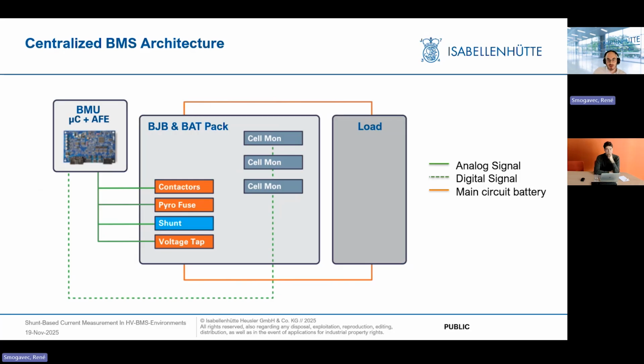So going into the architectures, between the extremes we have the centralized and the decentralized. In the decentralized architecture, the components communicate high quality signals in digital format to each other, such as over CAN bus. In centralized, the sensor and actuator data signals are processed centrally, handled and controlled by the BMU. The BMU roughly consists of the analog front end, the AFE, and a microcontroller, or whichever is needed for the signal processing. Part of the analog front end is the sensor element that feeds the AFE with an analog signal, for example the shunt.